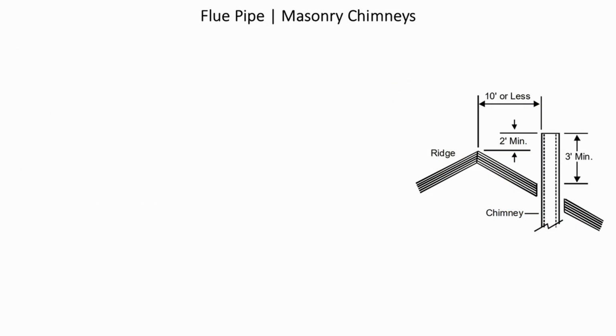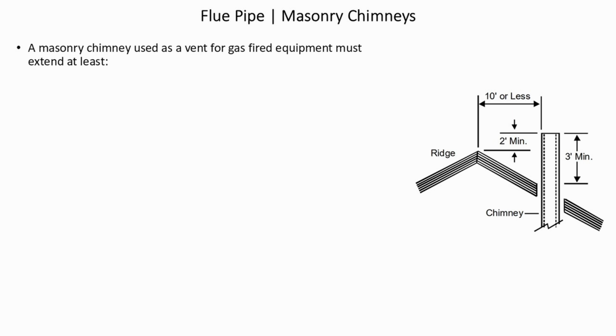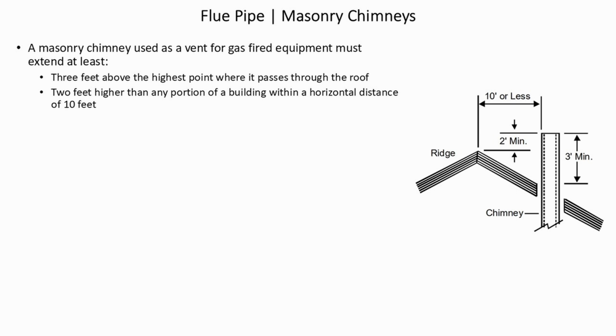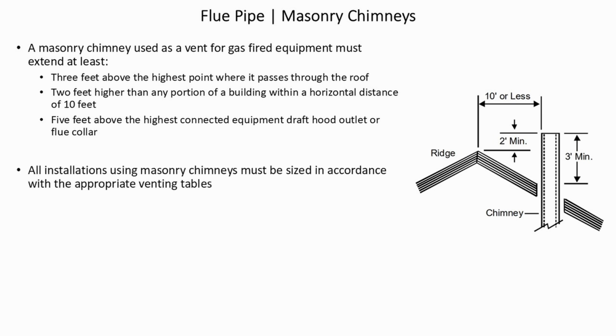Flue pipe in masonry chimneys. A masonry chimney used as a vent for gas-fired equipment must extend at least 3 feet above the highest point where it passes through the roof, 2 feet above any portion of the building within a horizontal distance of 10 feet, and 5 feet above the highest connected equipment draft hood outlet or flue collar. All installations using masonry chimneys must be sized in accordance with the appropriate venting tables.